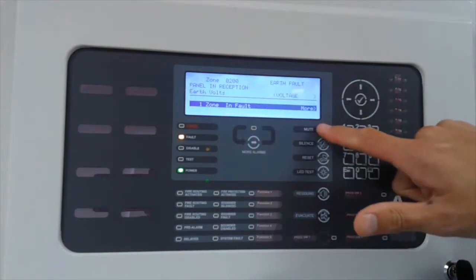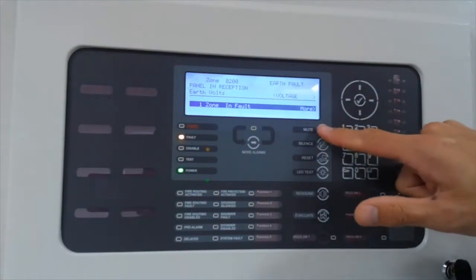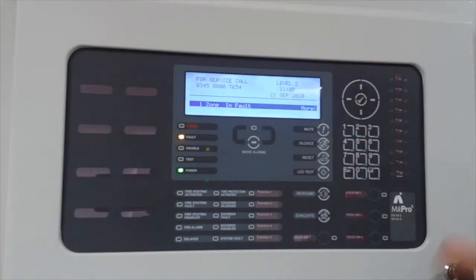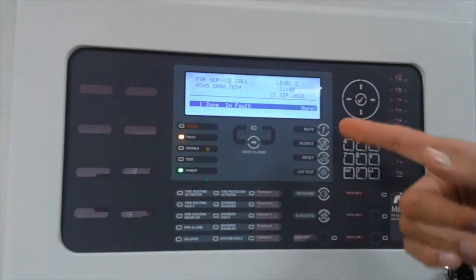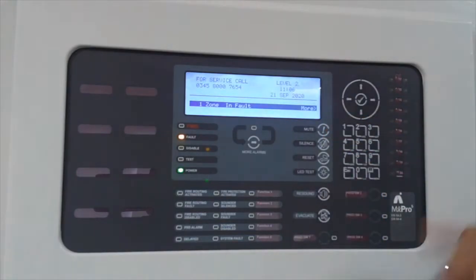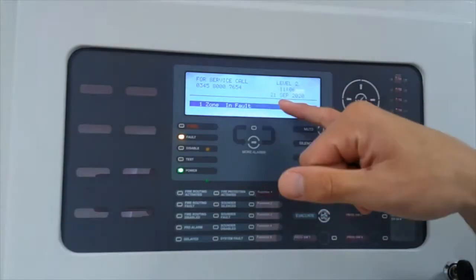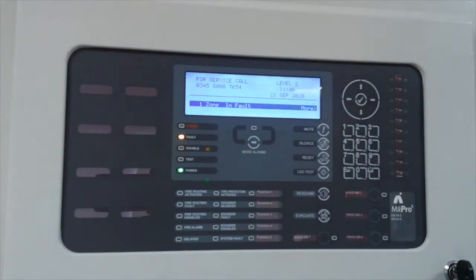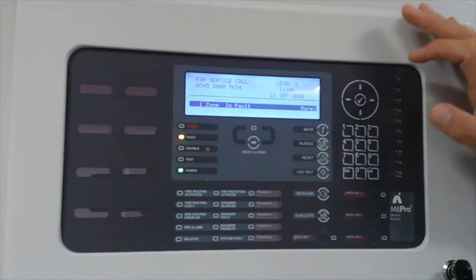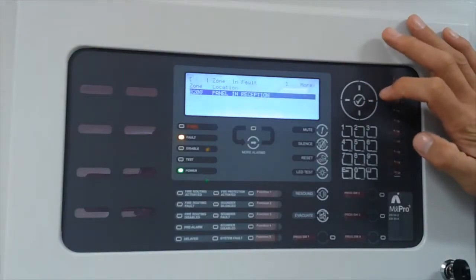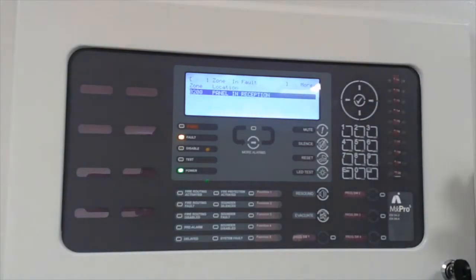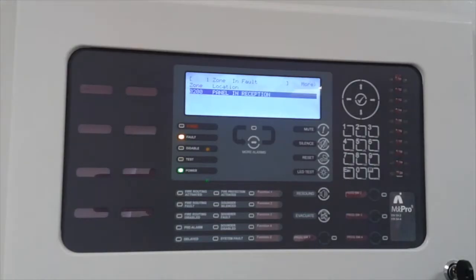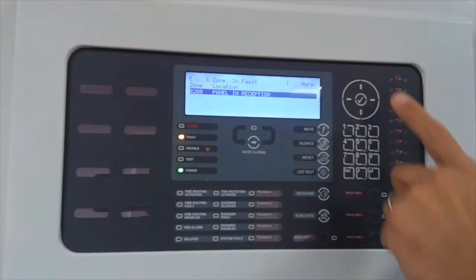So we can press the mute button, we are not affecting the operation of the system, we are just silencing the buzzer. You will notice the moment I press the mute button, that menu changed. It says for service call your telephone number. If you scroll to the right-hand side, one zone in fault, zone 200, zone 200 being the location of your control panel, and in this case the relevant text is being put in - it is the panel in reception.